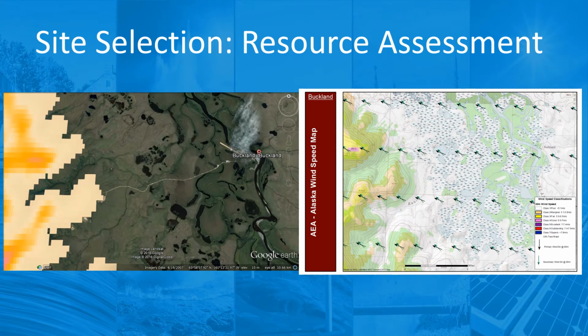The wind resource model is our first step in selecting a potential site. Sites close to the community are preferred if the wind resource is sufficient. Otherwise, look for a site close to existing power lines or roads. Greenfield sites are the least preferred unless they offer superior wind energy to offset higher costs of development, roads, transmission lines, and site communications. Determine how you will transport and erect a 30-meter or 50-meter MET tower at the proposed site.